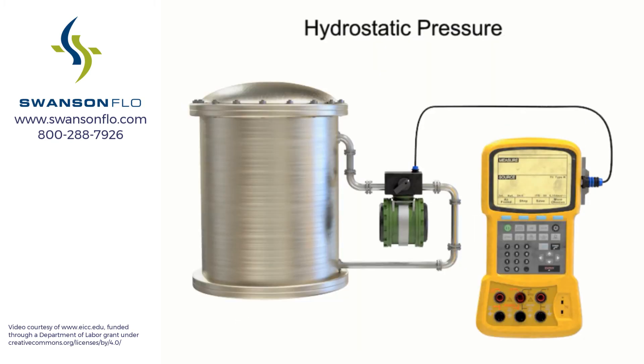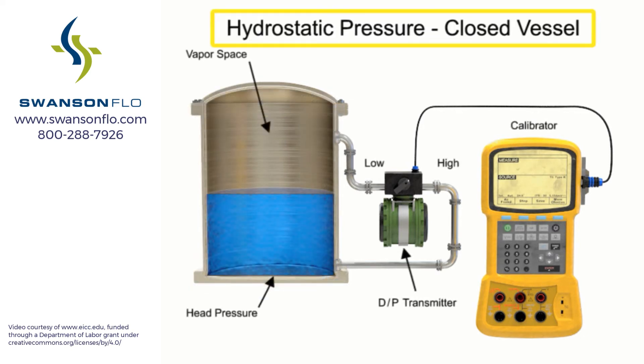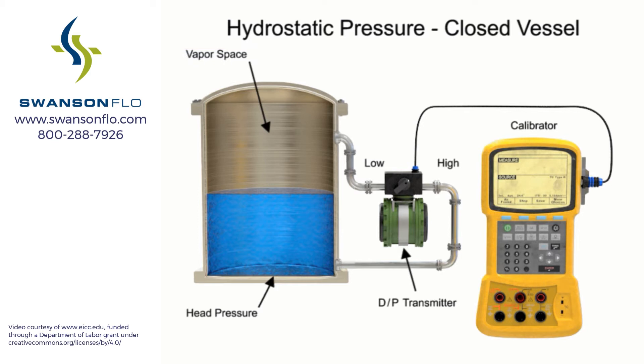Hydrostatic pressure can only be accurately calculated from an open container. Within a closed or pressurized vessel, the vapor space above the column of material adds pressure and results in inaccurate calculated values. The vessel pressure can be compensated for by using a differential pressure transmitter.